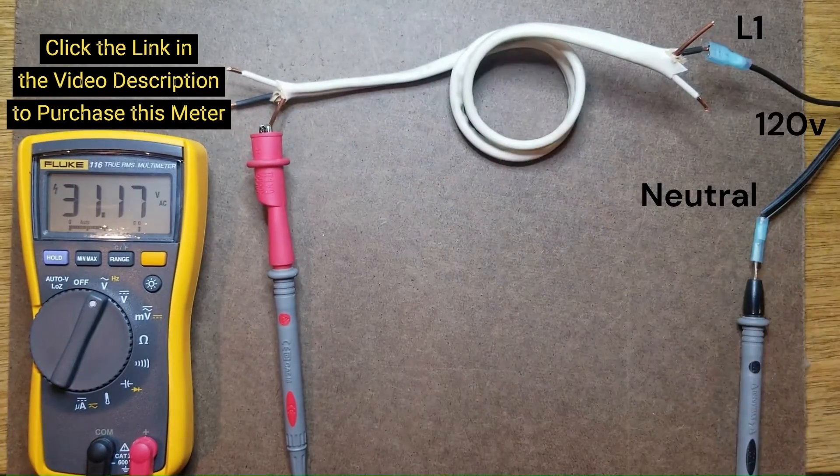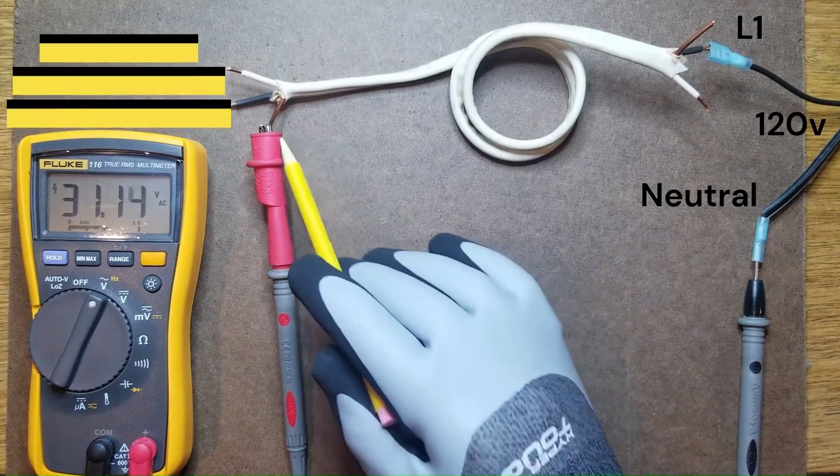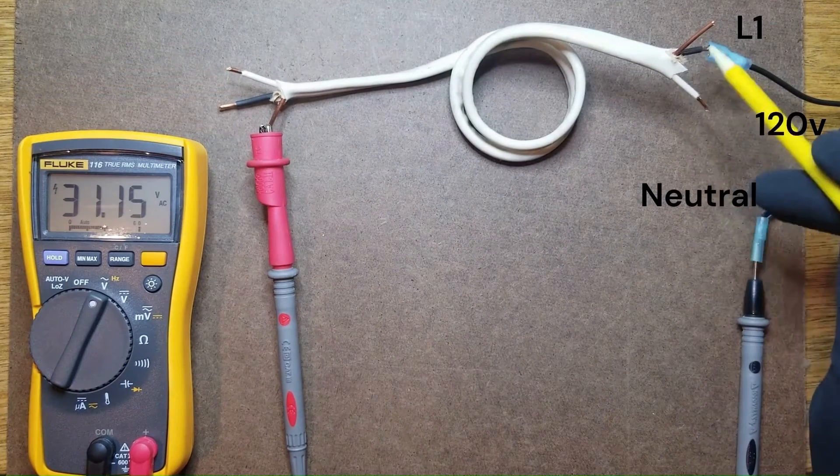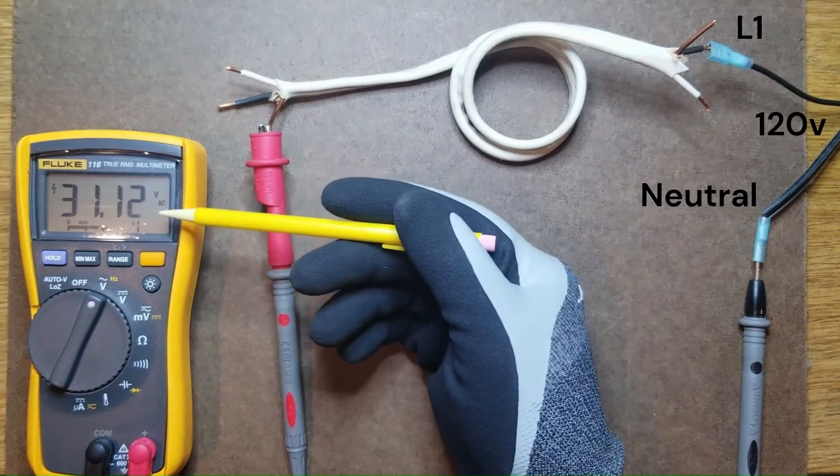It shouldn't have any voltage on at all. However, because of the proximity to the black wire and the capacitive coupling between the two, we're reading about 31 volts.